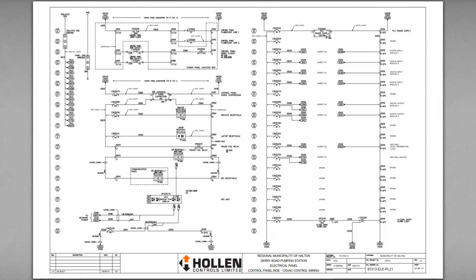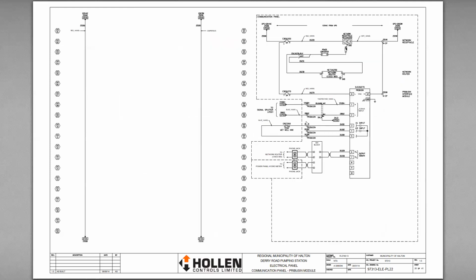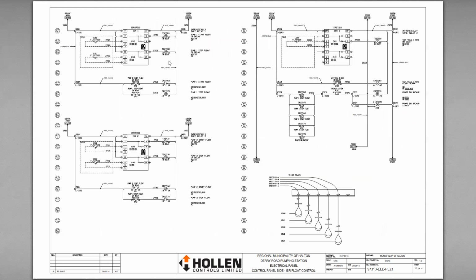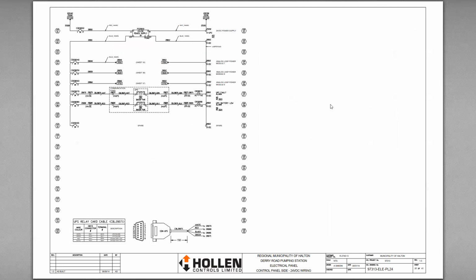So the UPS supplies power to the 24-volt power supply for the PLC. Then we have digital input modules, digital output modules, and power distribution, more power distribution for the network panel, power distribution for intrinsically safe relays, which are required when you wire floats from a sewage wet well into an electrical panel. You have to use equipment to electrically isolate it so you don't spark and cause an explosion.